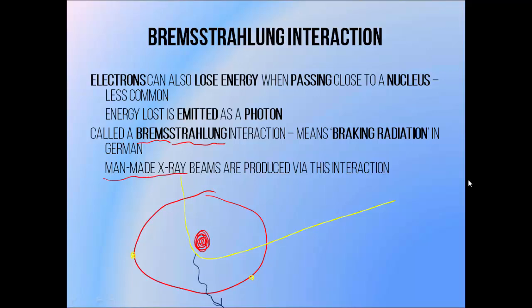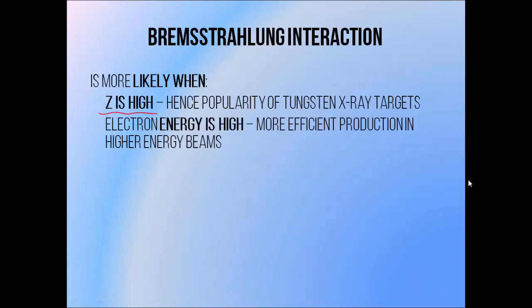It is via this process that X-ray tubes and linear accelerators are able to produce X-ray beams. We do this by slamming a high energy electron beam into a target material like tungsten. As it passes through the target, it undergoes the Bremsstrahlung interaction and produces photons. We use a high atomic number material like tungsten because the Bremsstrahlung interaction is much more likely when the atomic number is high, because the nuclear charge is greater, and therefore electrons passing through the material are more likely to interact with it.